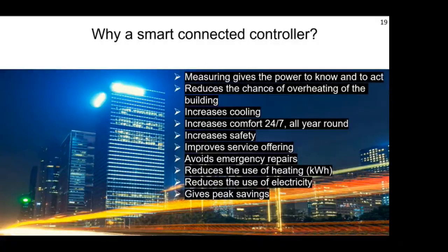Benefits of having a smart controller. By monitoring the substation and having remote access, you can implement changes quicker in real time. Monitoring also gives the ability to react to sudden changes in the system, which impact efficiency and the comfort, or the overheating or underheating, of the building, so you can tweak things quite quickly. By making small changes remotely, the substation efficiency can be increased by increasing the cooling and improving the delta T without multiple visits to site. So you haven't got an engineer tweaking differential pressure control valves or commissioning sets.